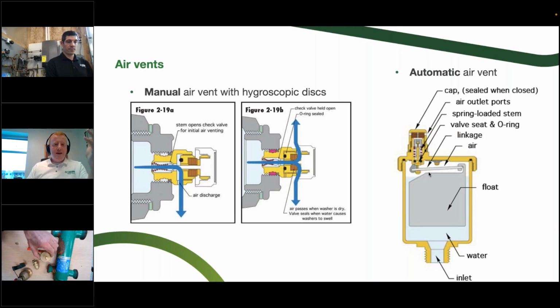So when you've got that air vent, that float moves up and down, and as the float moves up, it's because there's water pushing up from the bottom, and it floats up with that water. Now, you see a lot of guys in the field who don't know whether or not the air vent's working. So how else do you confirm that that air vent's working? You take that cap off the air vent and you push the needle down inside there.